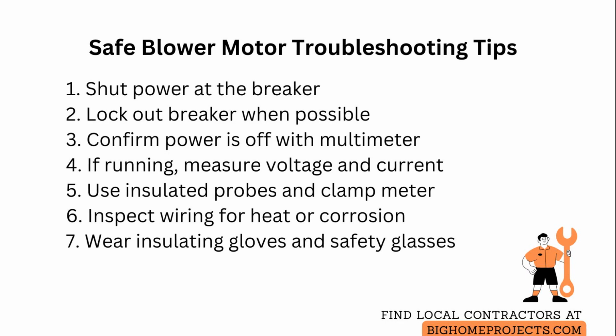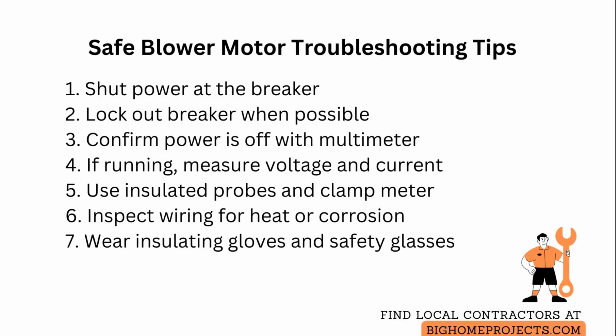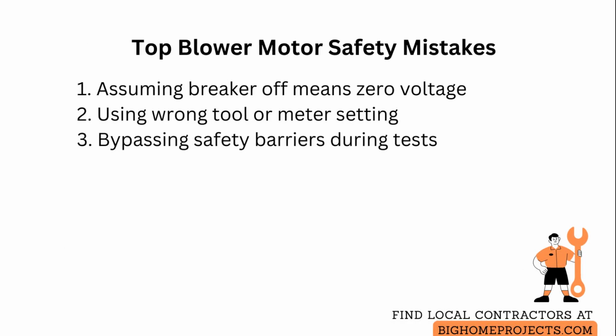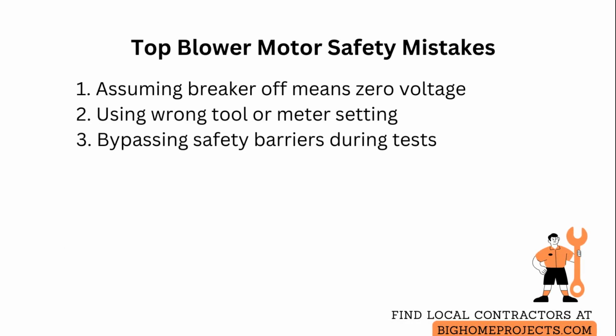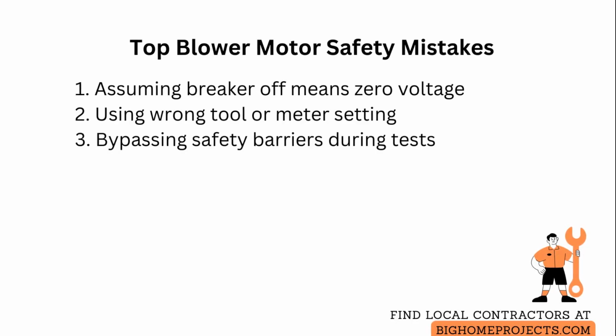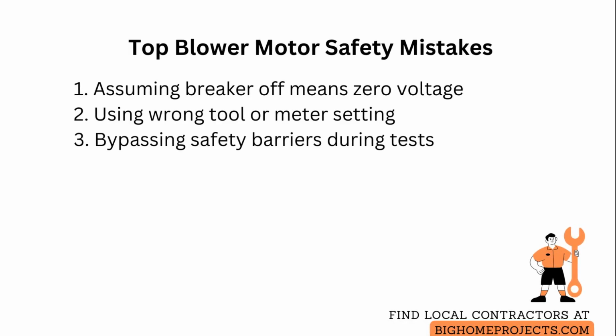If you are not trained in electrical diagnostics, hire a qualified technician to perform live testing rather than guessing or using improvised tools. Common mistakes include assuming the breaker off equals 0 voltage, which leads to accidental contact with live conductors. Always confirm with a multimeter at the point of work.